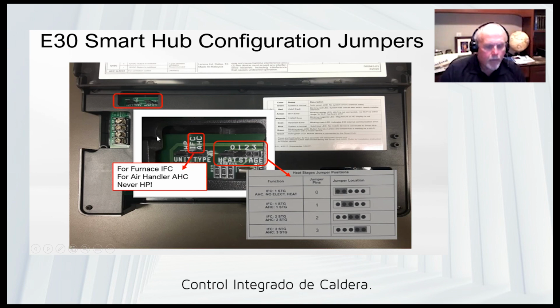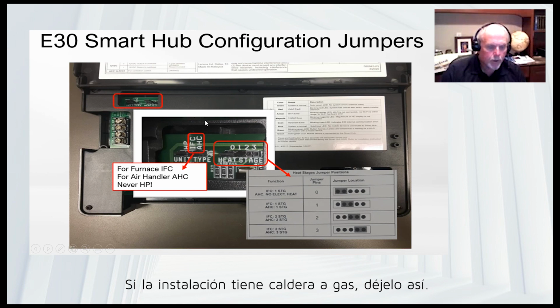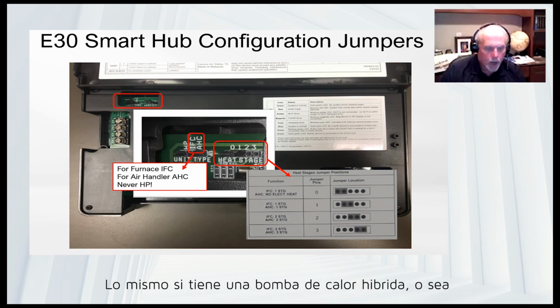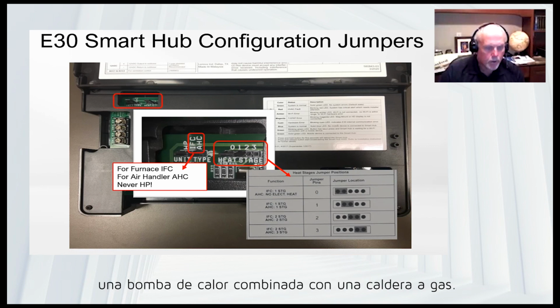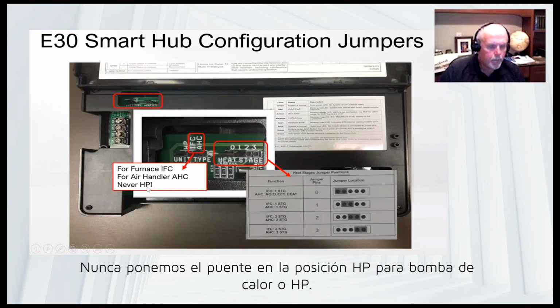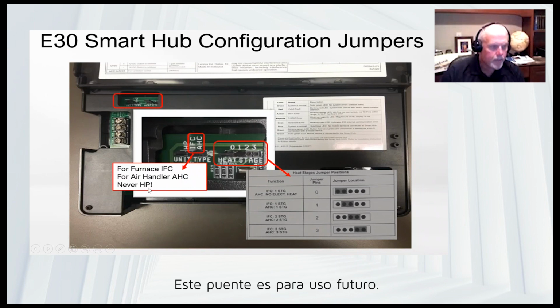Okay, it will be there. If you have a gas furnace involved with your system, it will be on IFC. Even if you have a heat pump for dual fuel operation, so if you have a hybrid system with a heat pump and a gas furnace, we call that dual fuel, it will still be on IFC. Okay, we never put it on heat pump, HP. We never put it there. That is for some kind of future use. But for the moment, for now, we do not use HP. Even if you have a heat pump with a gas furnace, you will put it on IFC.